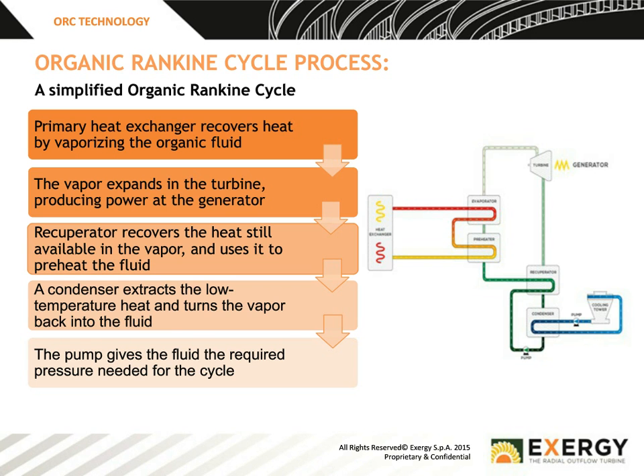So there would be no need to have an intermediate fluid if this heat is being recovered from a fluid in the first instance. So that intermediate or direct fluid passes through a heat exchanger, which is where it interacts with the organic Rankine cycle system. So the beauty of having this separate heat exchanger means that the process is not affected by the organic Rankine cycle. We are separating the two systems, with the only contact being this heat exchanger, which is always provided by the organic Rankine cycle supplier and is a key part of our equipment.